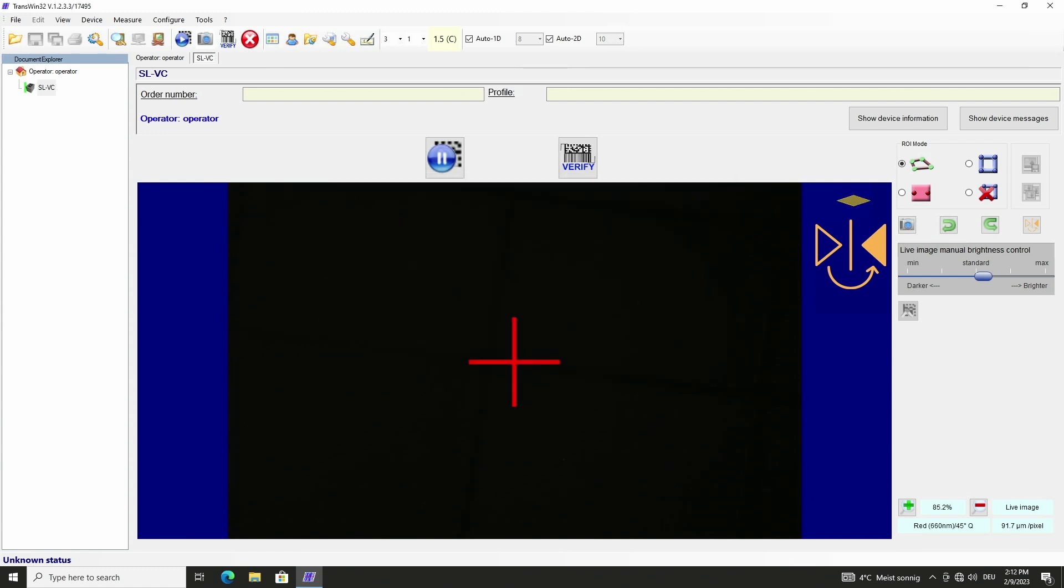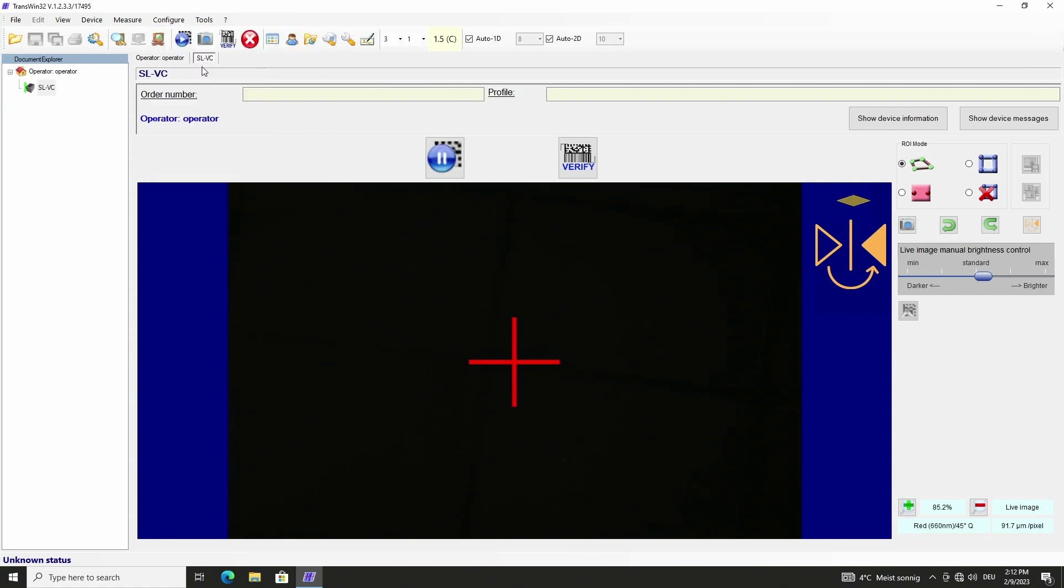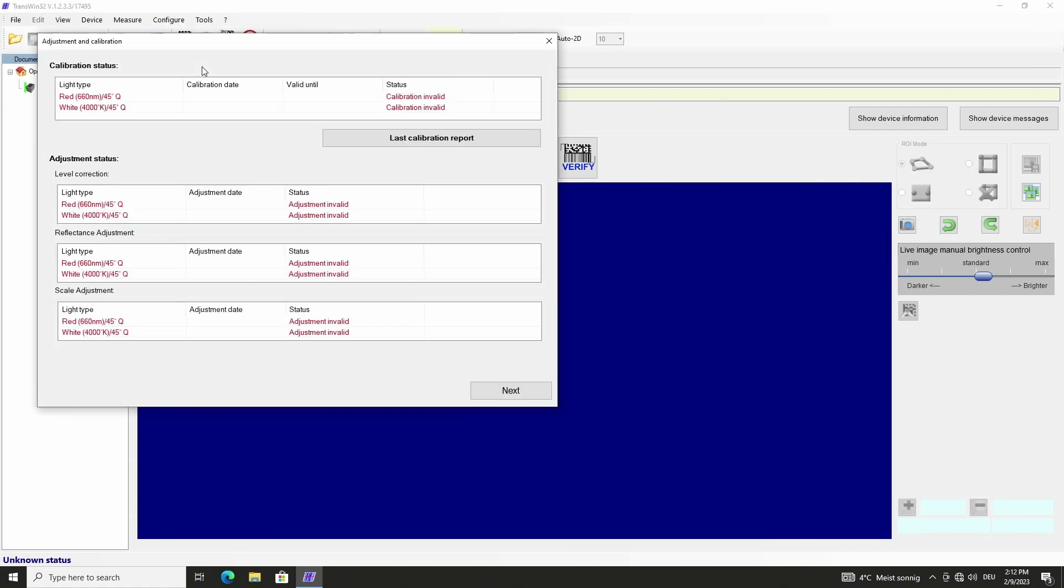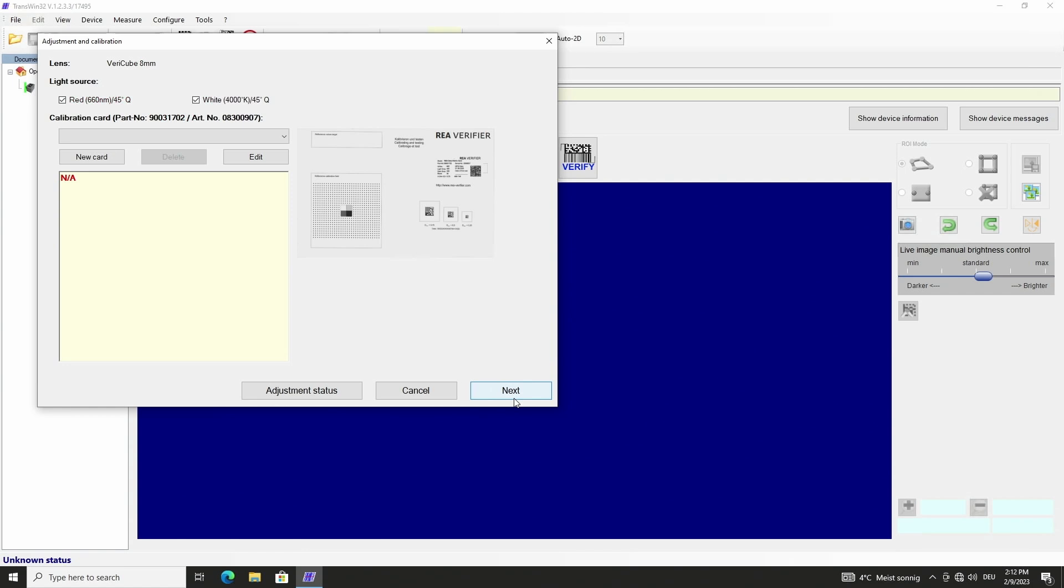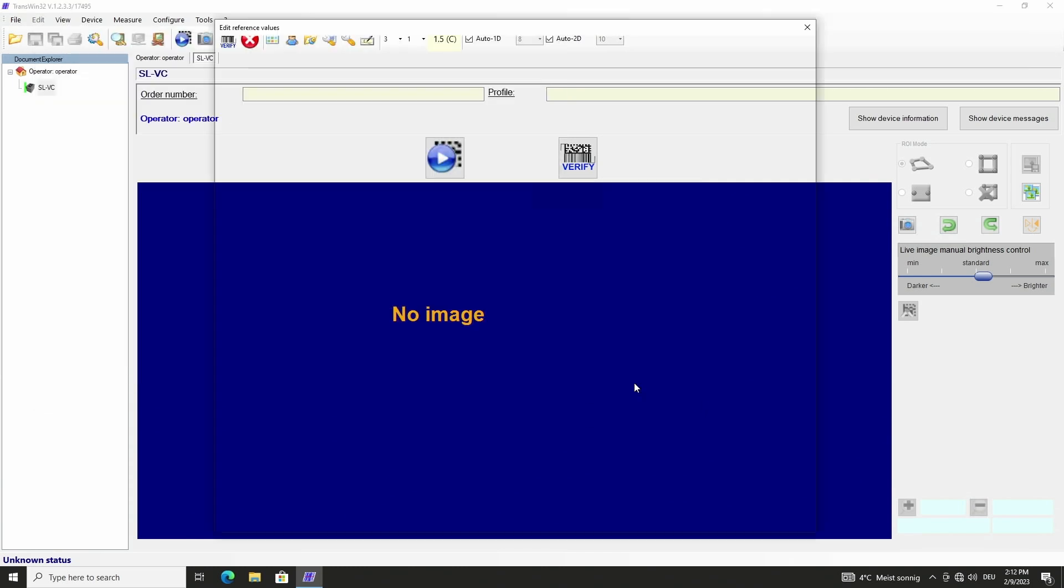The adjustment starts with menu item configure adjustment and calibration. The actual calibration and adjustment status is displayed. With next the software shows that no calibration card data is available and that we have to enter the values for a new card. With OK we can enter the data.